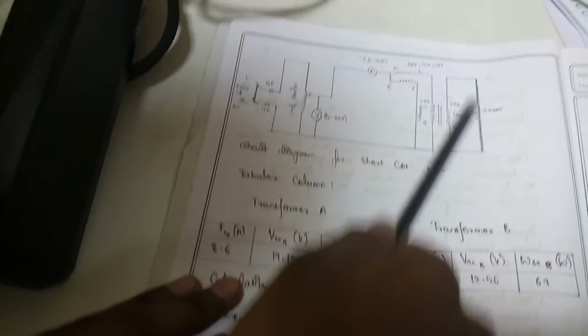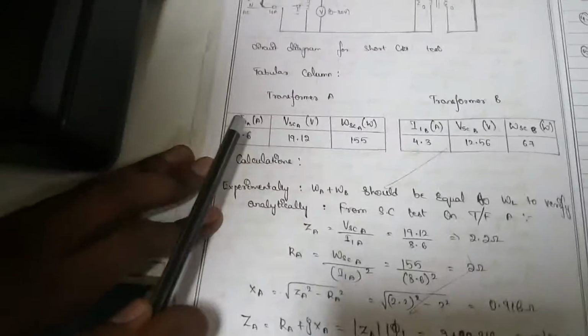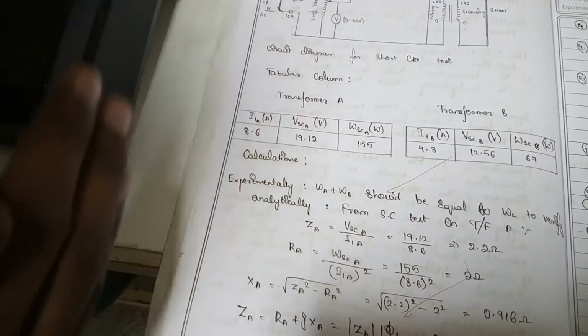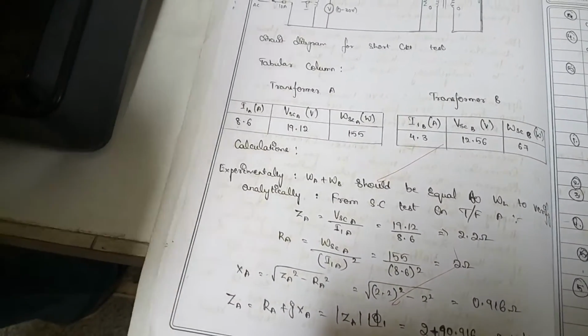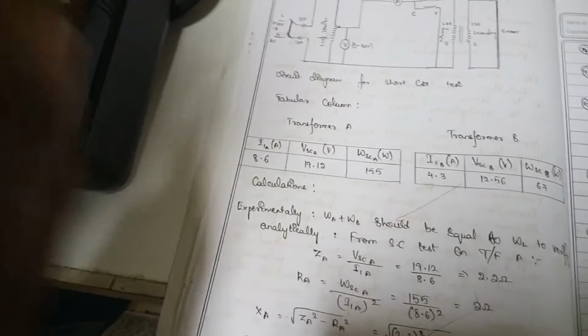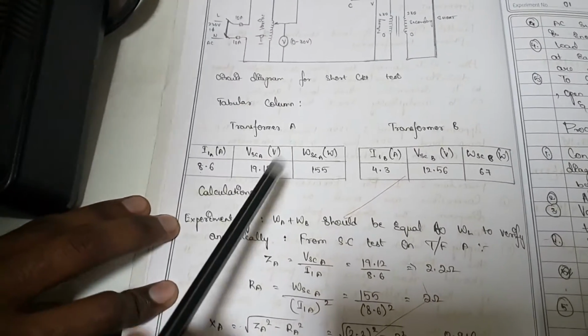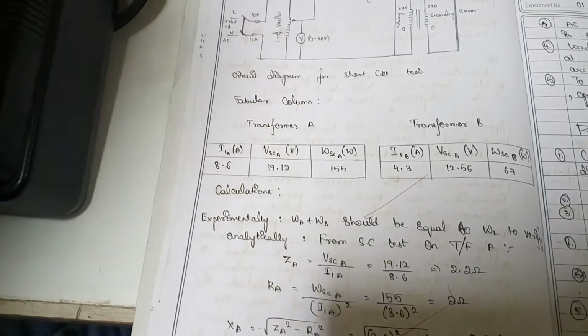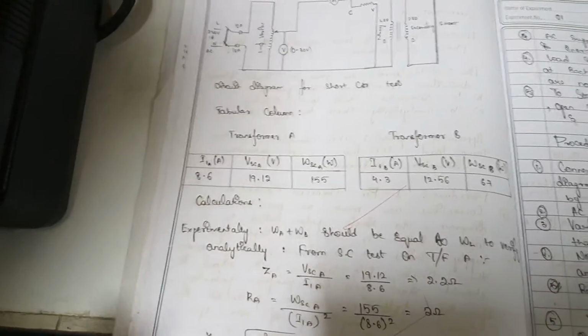Now see, this is a short circuit test, which means the secondary should be shorted. We have shorted this, and we will be taking these readings. There will be two transformers, we have taken 2 kVA and 1 kVA. So we will be doing the short circuit test for both transformers, 2 kVA and 1 kVA. And keep in mind that the short circuit test will be done under the rated current only. So we will be taking the rated current only.